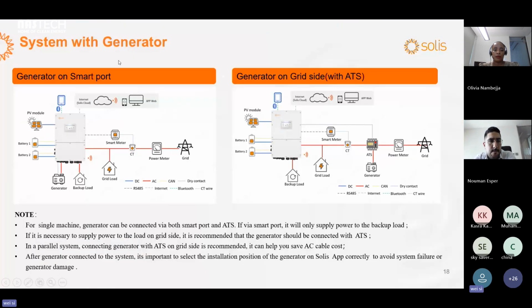About the generator, we support two methods of generator connection. One is to connect to the smart port. The other is on the grid side. If you want to connect the generator with automatic start and stop control, you should buy the ATS yourself and install it on the grid side, and the generator will start or stop based on the battery SOC.